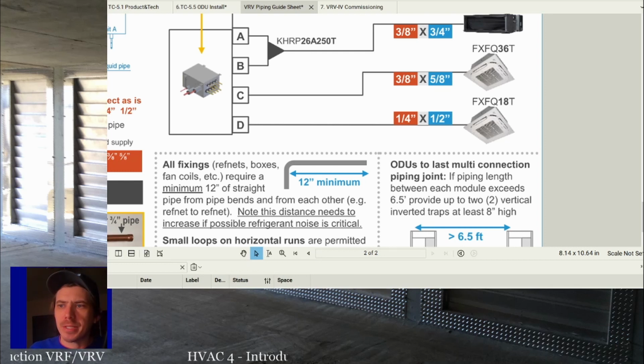Always, always, always, when it comes to these systems, it is utility over beauty. You want a system that works, not a system that's pretty. That doesn't mean do a garbage job, but if you can avoid brazing in a 90 and just bend the pipe to where it needs to go, then do that. It's extremely important to minimize potential leaks and changes in direction that increase the overall length. Remember, a refrigerant 90 basically counts as 5 feet of pipe. So if you add five 90s, you added 25 feet of pipe, whereas if you just bent it where it needed to go, you didn't add any extra length. So just something to keep in mind.